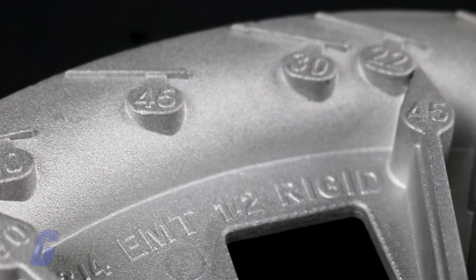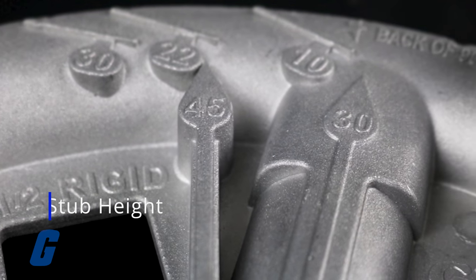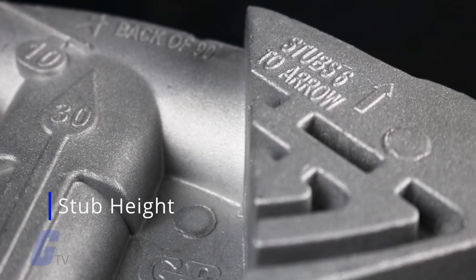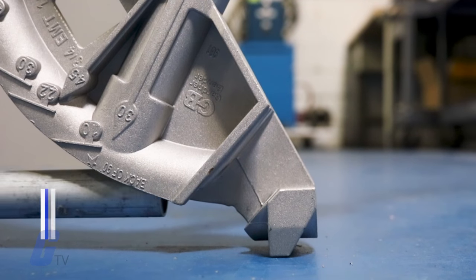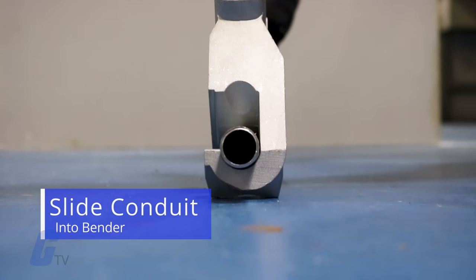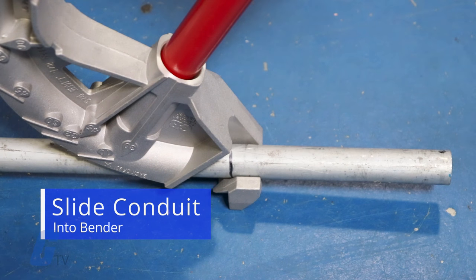Finally, you will often find a stub height mark. This mark will usually list a number like 6 inches to use for the bender take-up. Slide the conduit into the bender, leaving the appropriate amount past the arrow on the bending shoe.